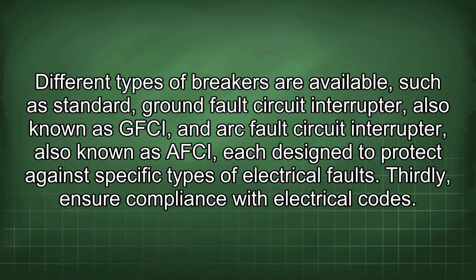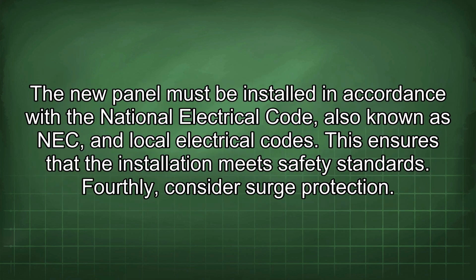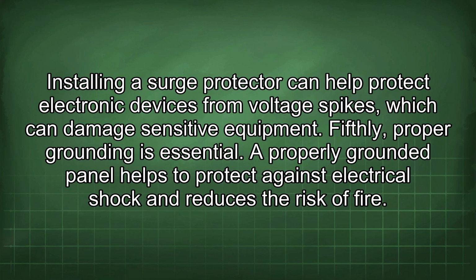Thirdly, ensure compliance with electrical codes. The new panel must be installed in accordance with the National Electrical Code, also known as NEC, and local electrical codes. This ensures that the installation meets safety standards. Fourthly, consider surge protection. Installing a surge protector can help protect electronic devices from voltage spikes, which can damage sensitive equipment. Fifthly, proper grounding is essential.